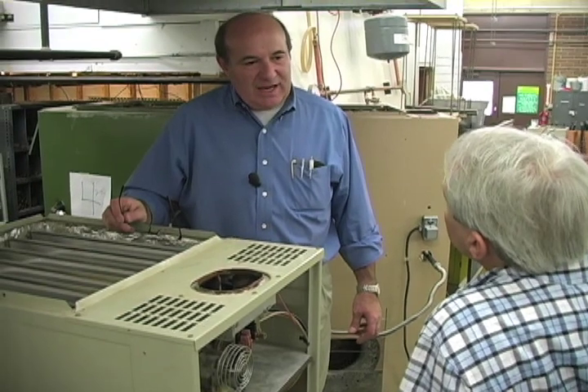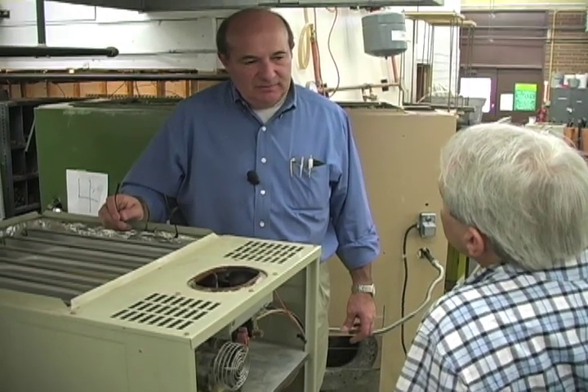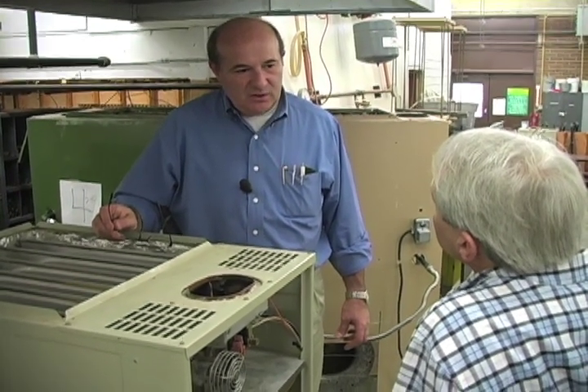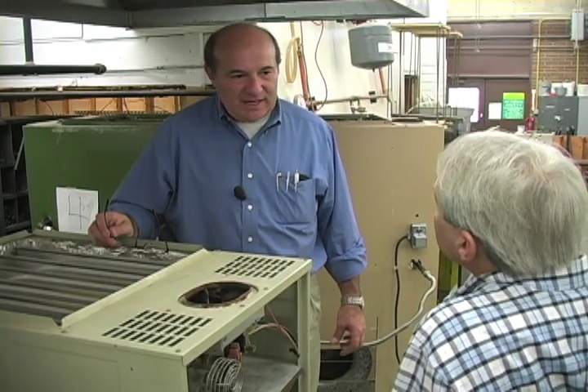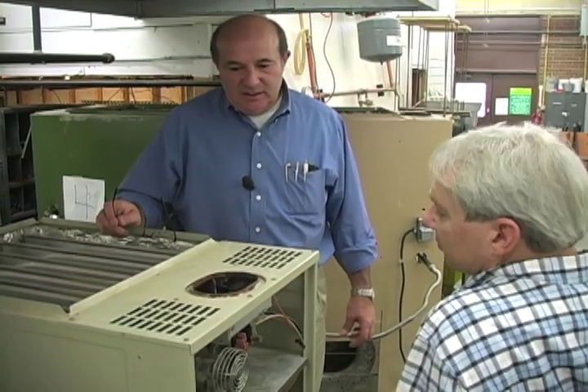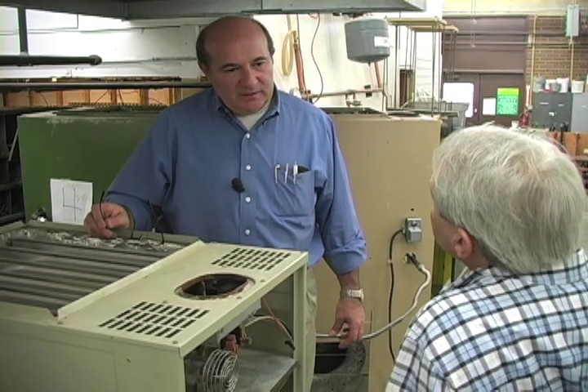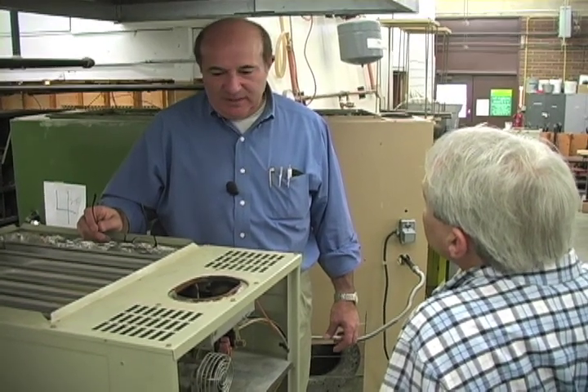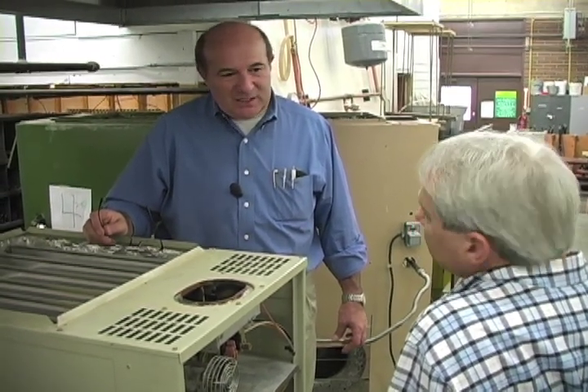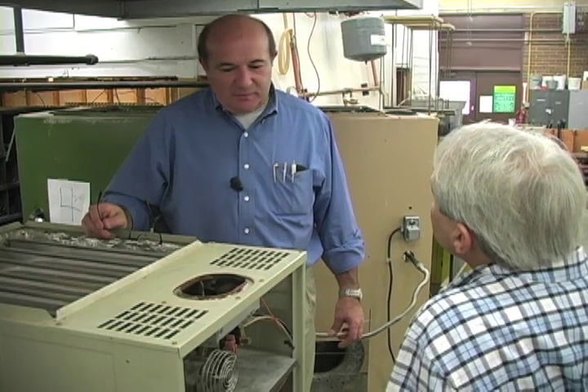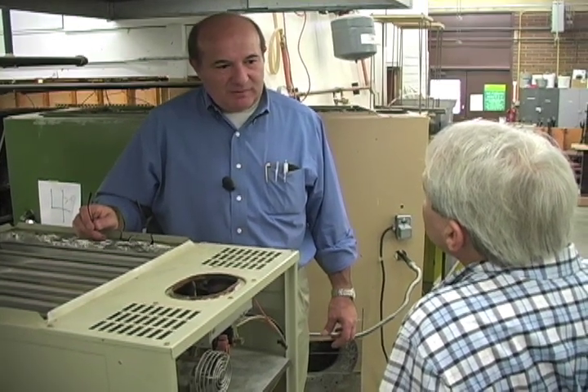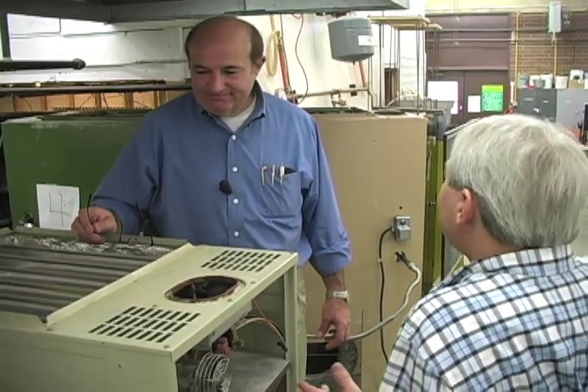And there are vent tables that you can go to, either in the National Fuel Gas Code or International Fuel Gas Code or the GAMA codes, and they'll tell you what the minimum sizes for those pipes need to be. But an oversized pipe can be as big a problem as an undersized pipe. Slows things down, slows gases down.